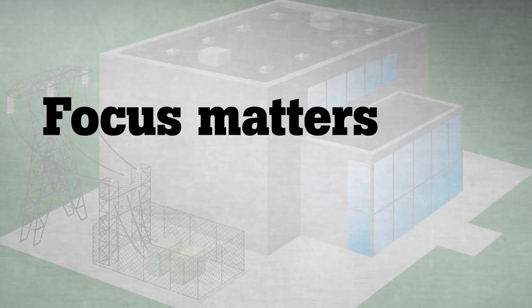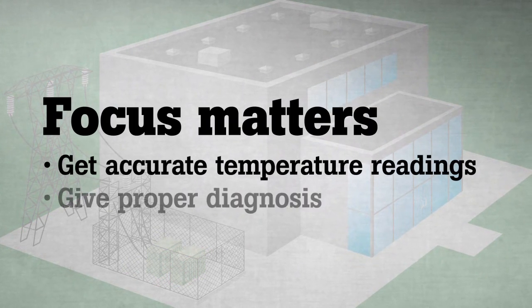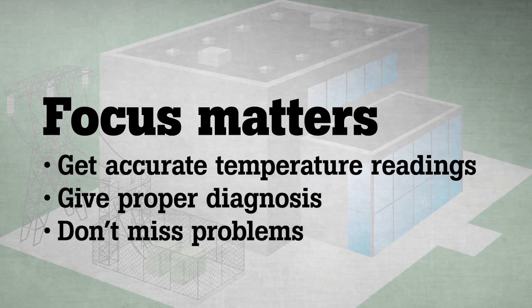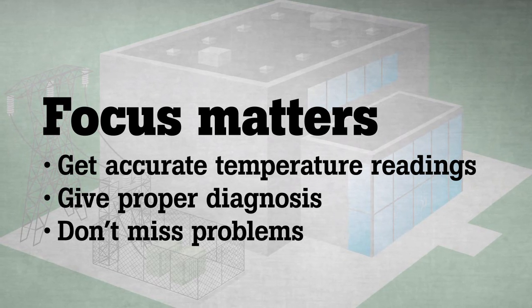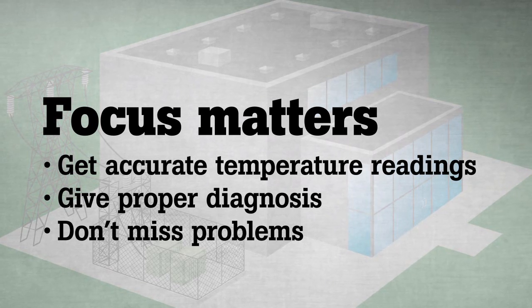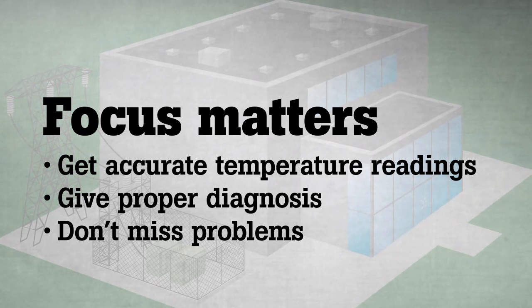Every infrared camera user knows that focus is the single most important thing to ensure when conducting an infrared inspection. Without an in-focus image, temperature measurements are often not as accurate, sometimes by as much as 20 degrees, and out-of-focus images make it much easier to miss a problem.